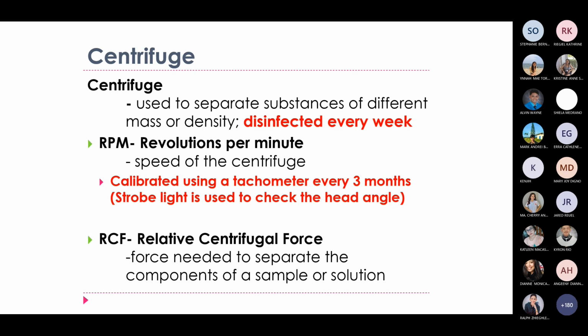So RCF is equal to the RPM squared multiplied by 1.118 times 10 to the negative 5 times R. Ano kaya ang ibig sabihin ng R? That is the radius. Radius, which is in centimeters.